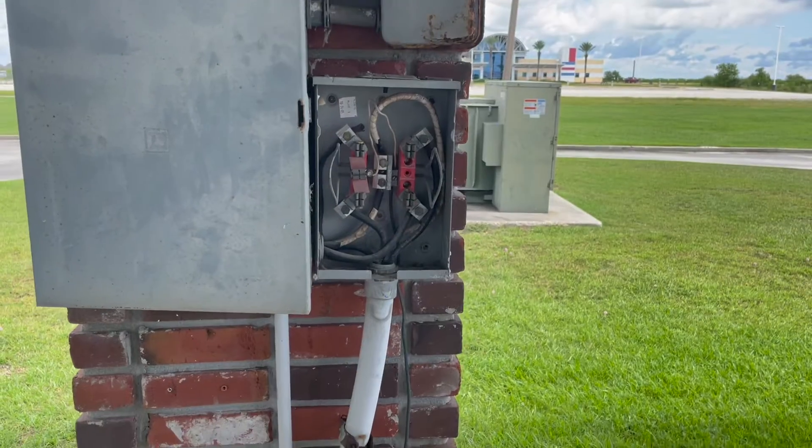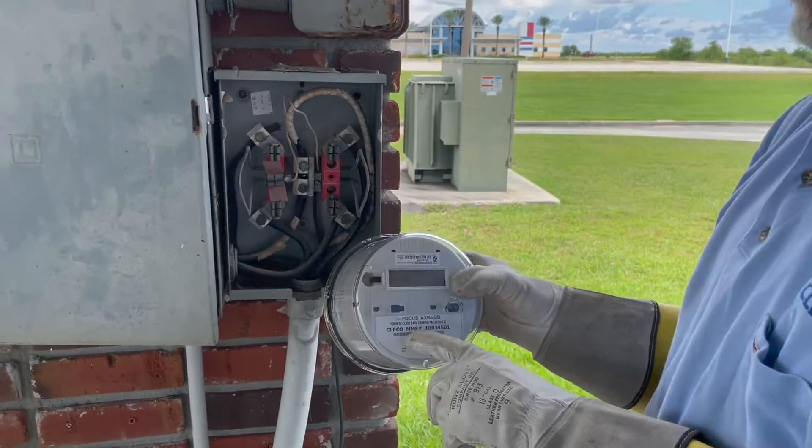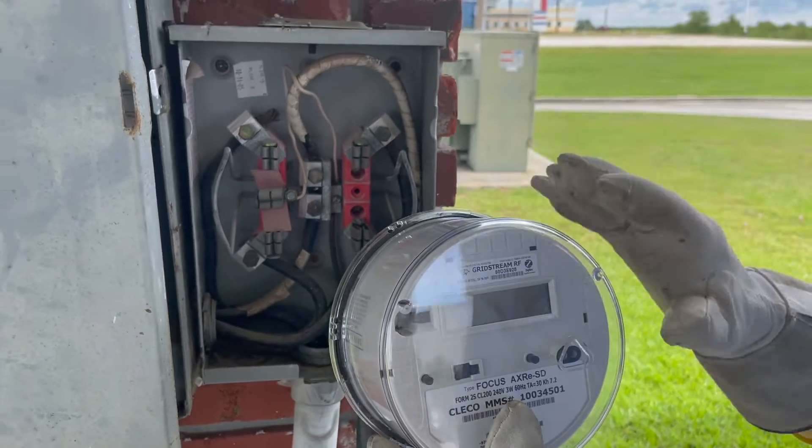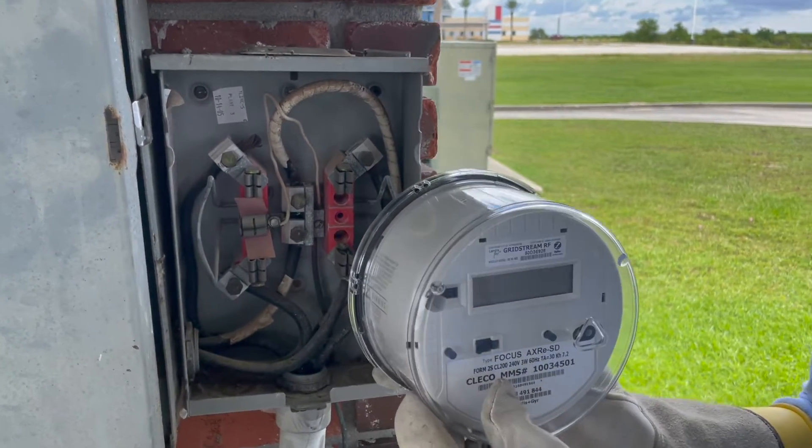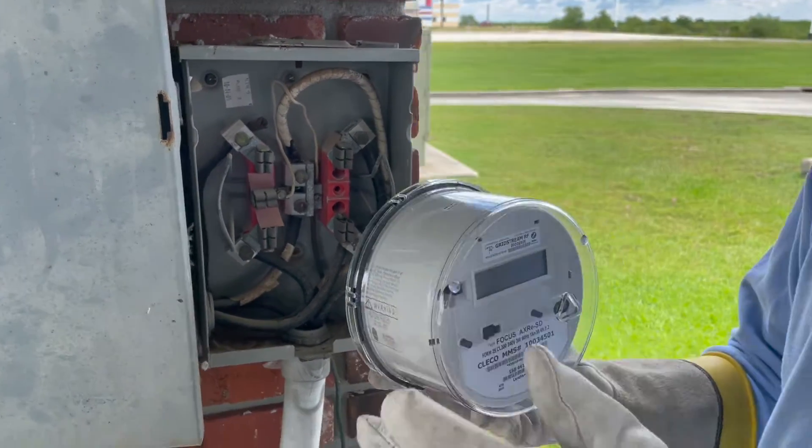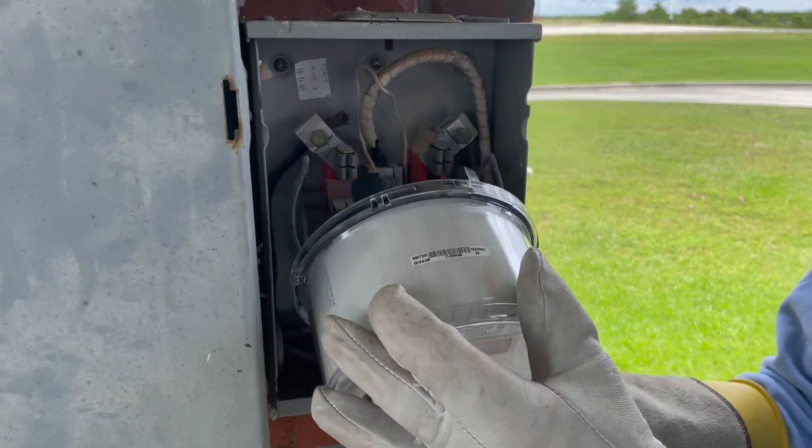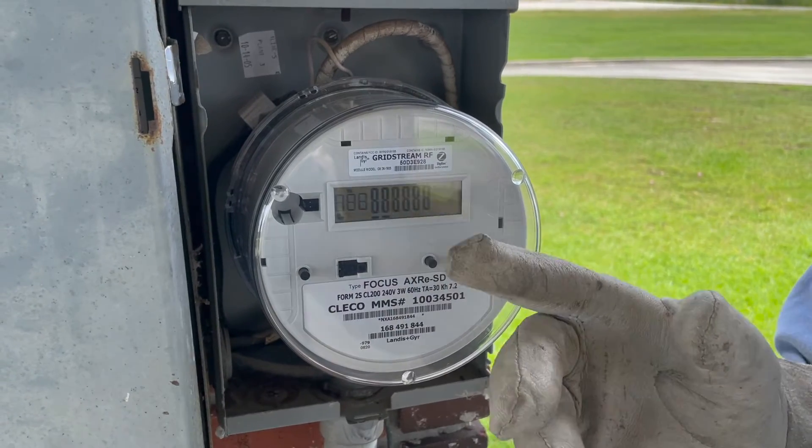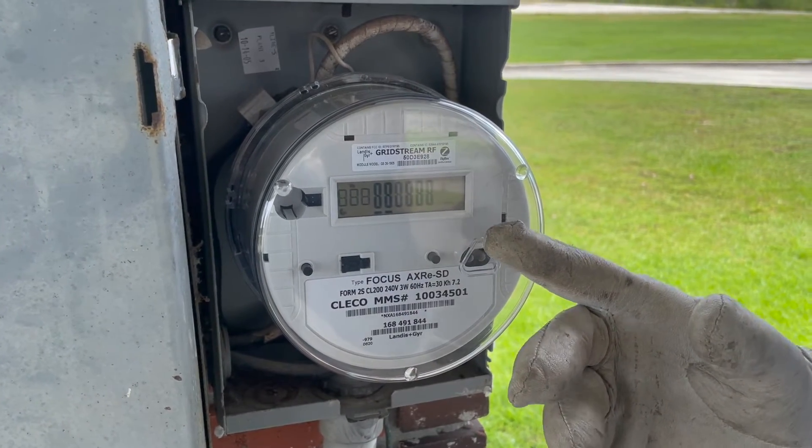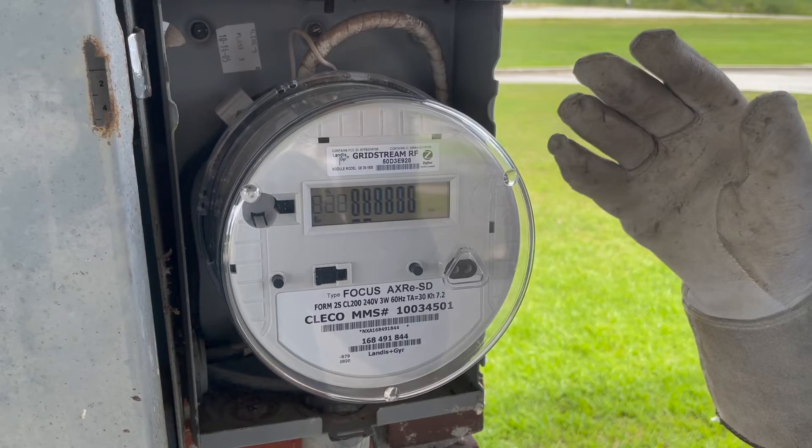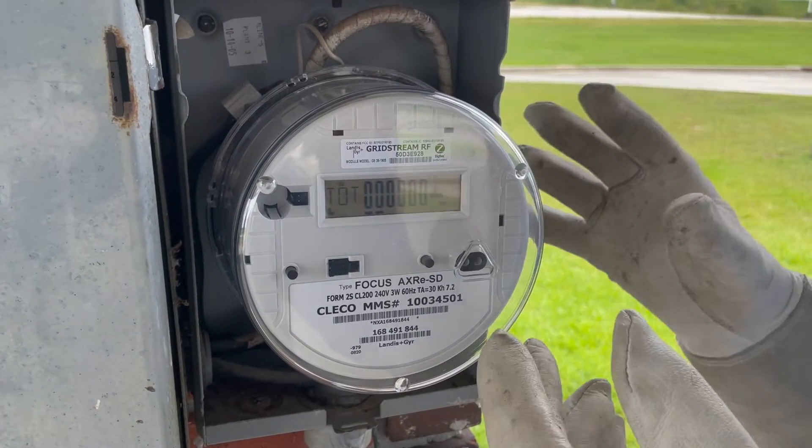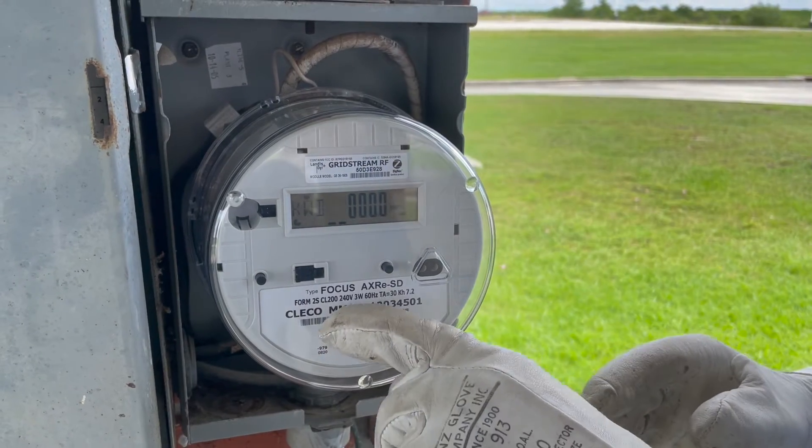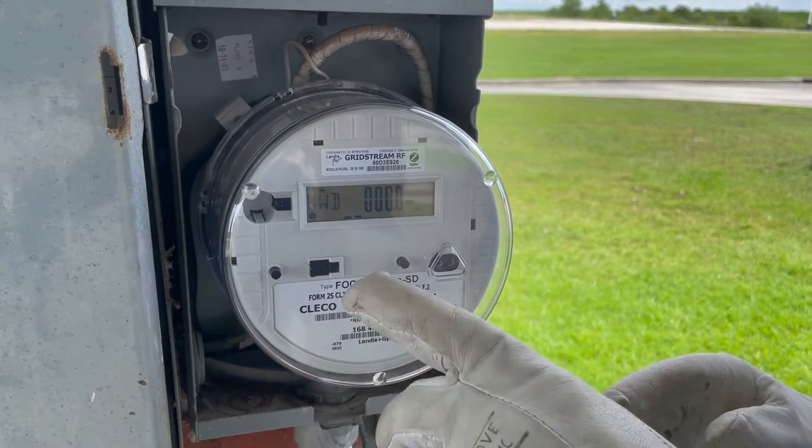What we have a problem with is servicemen come in here and they put in a form 2S, which is a 240 volt meter. These meters, when plugged into this situation, they will light up. So the meter lights up, the serviceman thinks he did everything right, but he did not check the voltages correctly. This is a Y network 120/208 instead of a 240 volt delta service.